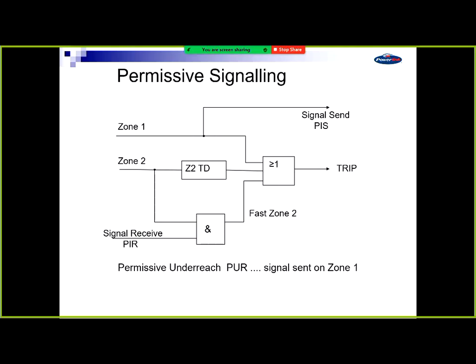The logic of it looks like that, a permissive underreach. So zone 1 goes through and trips. Zone 2 goes through at zone 2 time delay, typically 400 milliseconds, and trips. And zone 2 and a receipt for the signal from the remote end just goes through and trips. So the difference between zone 1 and zone 2 time tripping is just the protection signalling time delay, which is usually in the order of 20 milliseconds, 15 milliseconds. So it's quite quick.